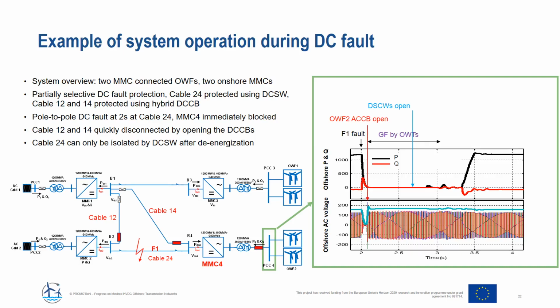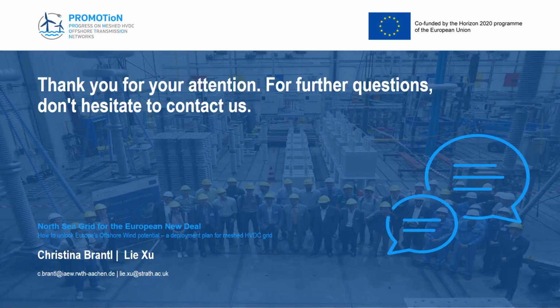offshore converter and the network. The offshore AC circuit breaker can then be closed and MMC4 re-energized. Cable 14 is then connected to the offshore system, and the normal power generation can be restored. So from this example, it can be seen that the additional wind turbine control functionalities help to maintain the offshore system during the DC fault transient and ensure fast system restoration after fault isolation.